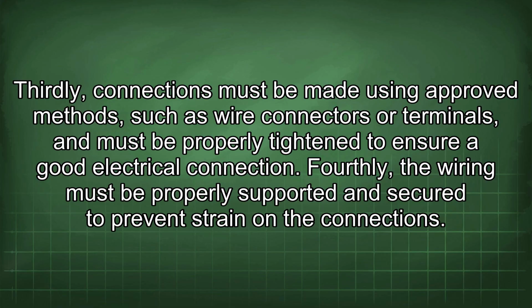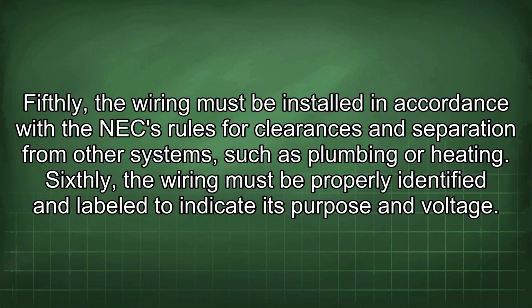Fourthly, the wiring must be properly supported and secured to prevent strain on the connections. Fifthly, the wiring must be installed in accordance with the NEC rules for clearances and separation from other systems, such as plumbing or heating. Sixthly, the wiring must be properly identified and labeled to indicate its purpose and voltage.